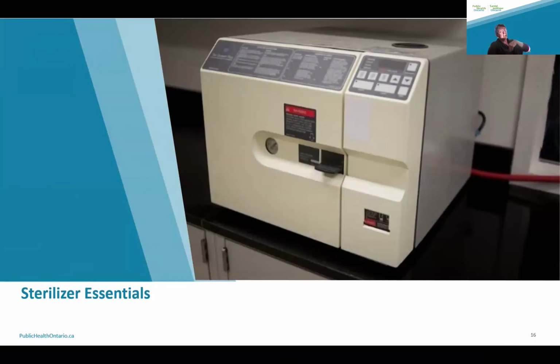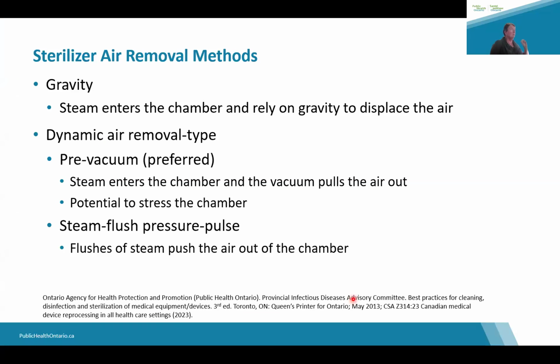All right, now we're going to dive even deeper into sterilizers. And I'm sure you're thinking, oh, enough already, but it's really important to understand. Okay, first of all, there are 3 types of autoclaves. The ones that are typically used are gravity, a pre-vacuum, or a steam flush pressure pulse. Try saying that fast 3 times. It's really hard. So, as you could guess, the gravity machine relies on gravity to push the steam in and relies on gravity to displace the air out the bottom of the autoclave.